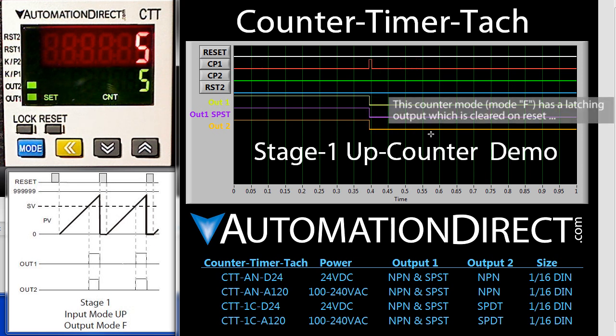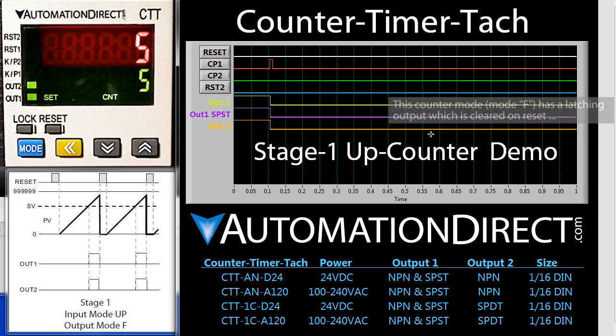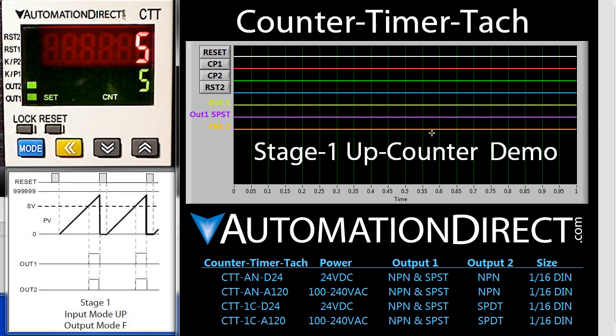All of these signals go low because output 1 has an NPN or sinking output and an SPST relay output. Output 2 has an NPN sinking output because we are using this model of the counter timer tach with an NPN output. You can also get it with a relay output and you can get both of those in a DC model. We are currently using the AC version right here.